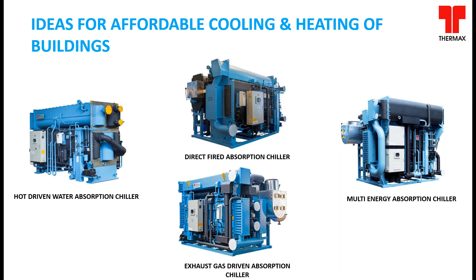Before moving on to the details of each of these absorption chillers, we can try to understand a small comparison between the electrical chiller and absorption chiller in terms of their efficiencies. In chiller technologies, we call this the COP, or the coefficient of performance. It is nothing but a measure of how well the energy that is used to drive the equipment is getting utilized. So it is a ratio of the cooling produced upon the energy that is used to drive it. In case of an electrical chiller, we will normally find that the COP is close to 5. Whereas in case of an absorption chiller, it varies from 0.8 to 1.8.